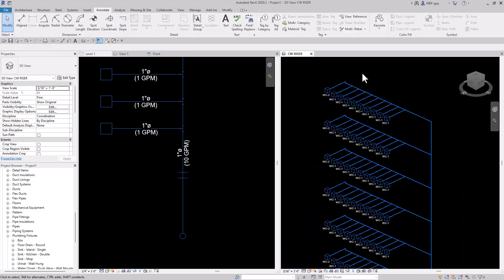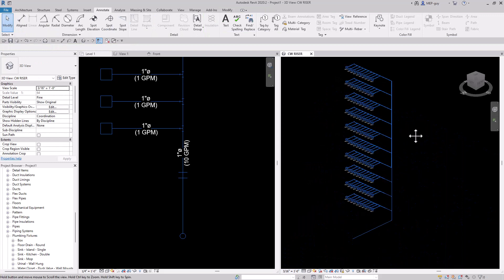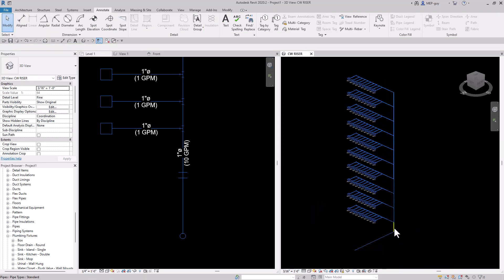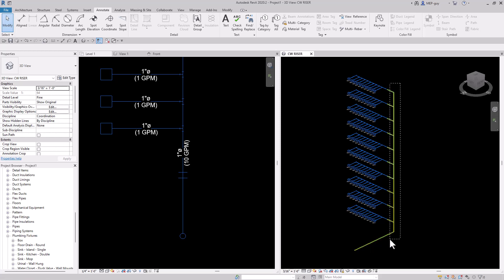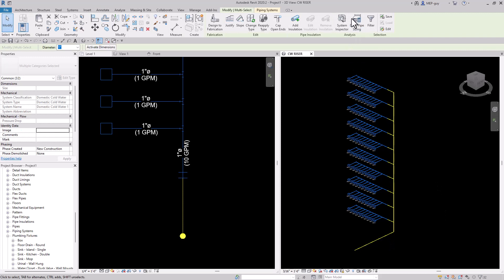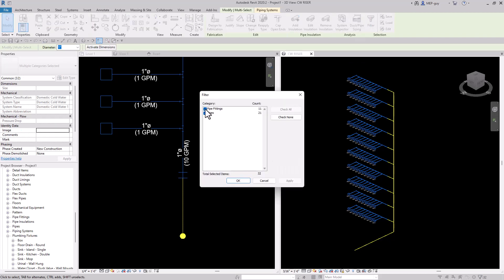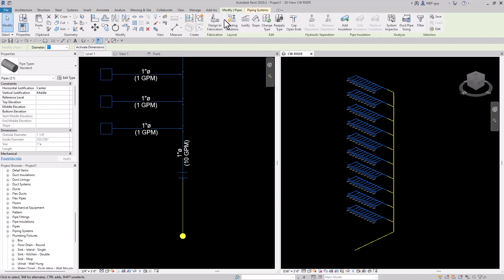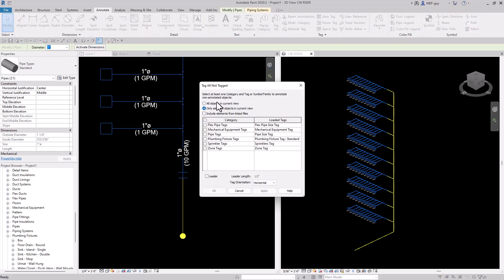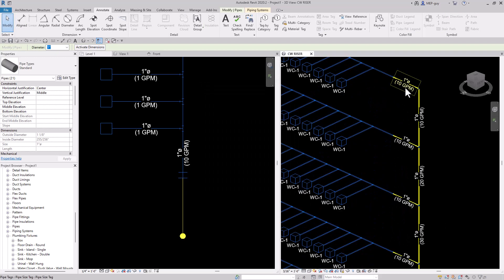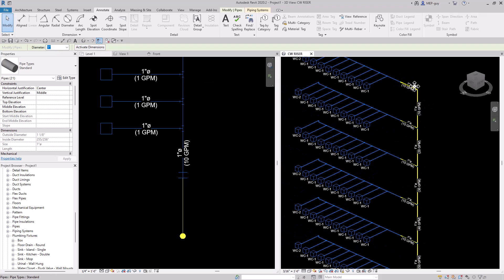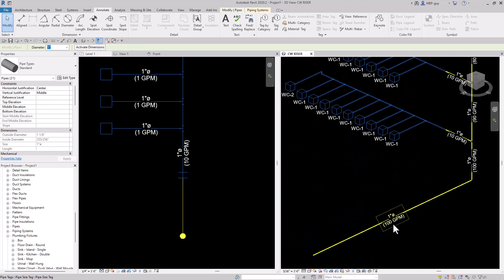That looks really good. The last thing I might want to do is tag all of my pieces of pipe. I'll select the pieces I want to tag, click the filter button, and deselect pipe fittings. Then go to annotate, tag all, using only the selected objects with the pipe tag we had before. We are tracking the GPM and pipe size as we go down to the bottom of our building, which is now 100 GPM.